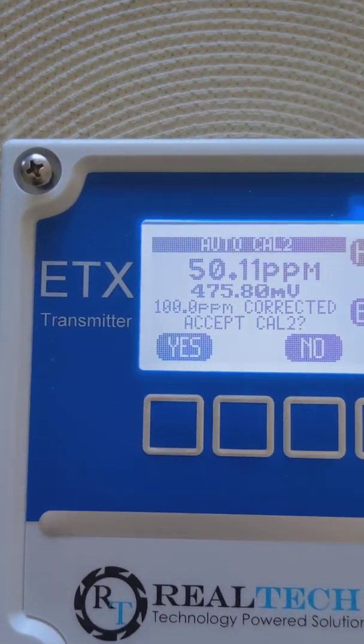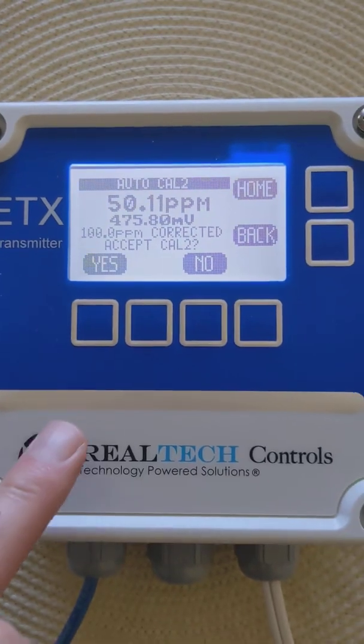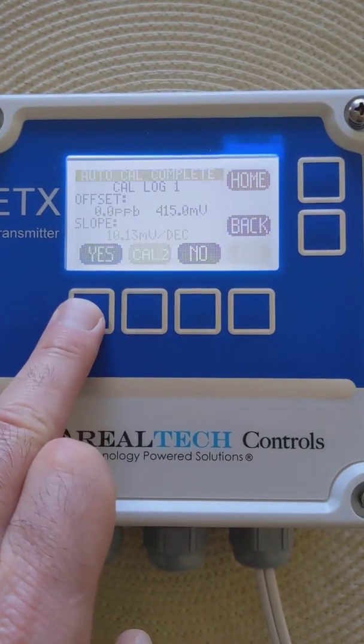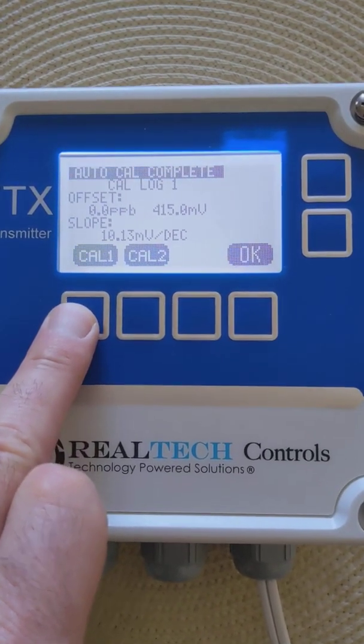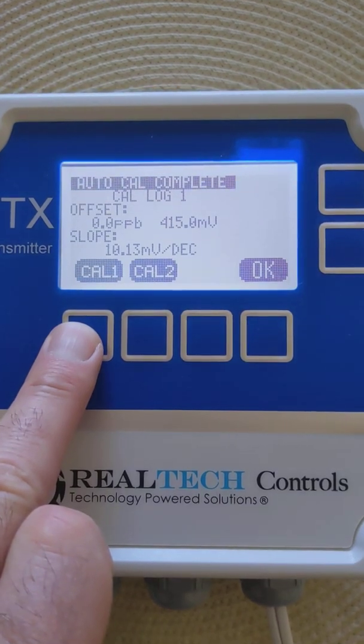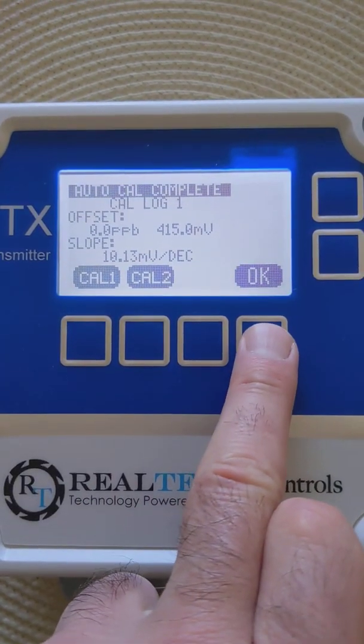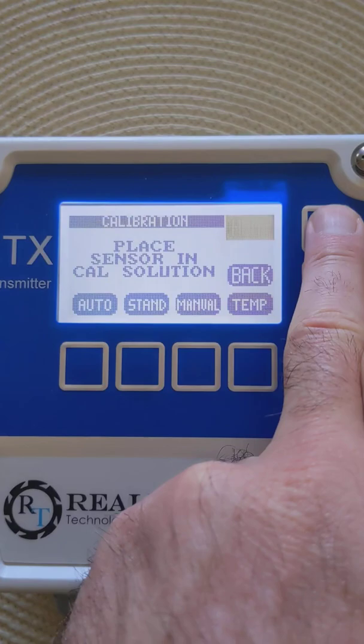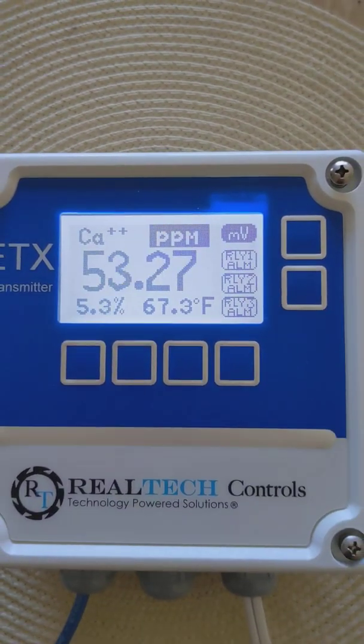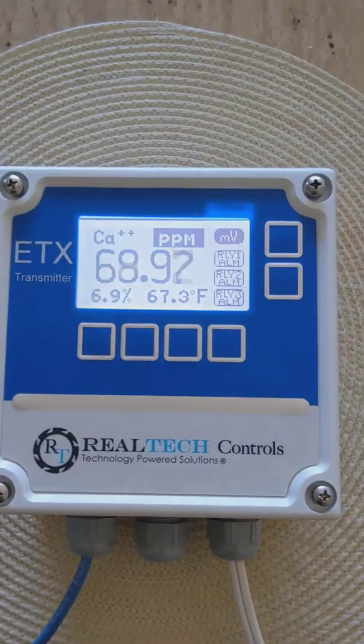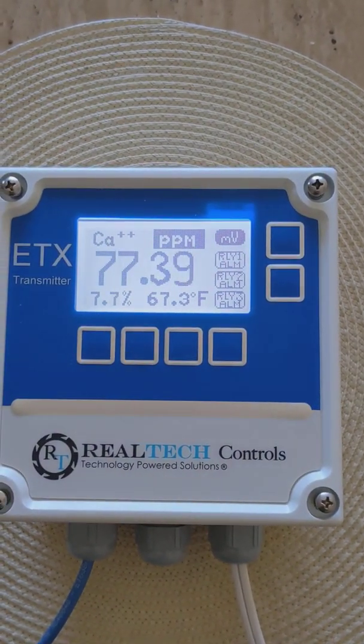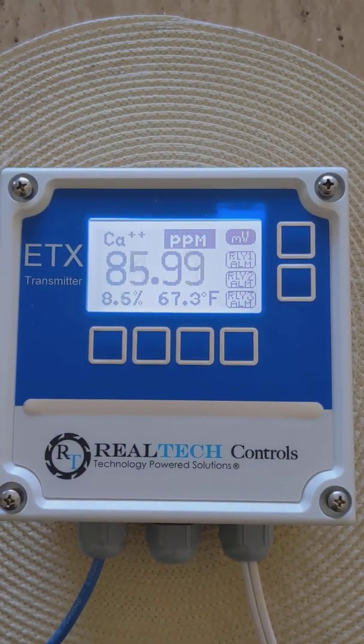It did accept it. So that's 100 ppm. We push yes. And that gives you your information on your offset and your slope, the new values. Push OK and exit. So with my sensor still in the city water solution, of which we've said is 100 ppm, the sensor should go to close to 100 ppm.